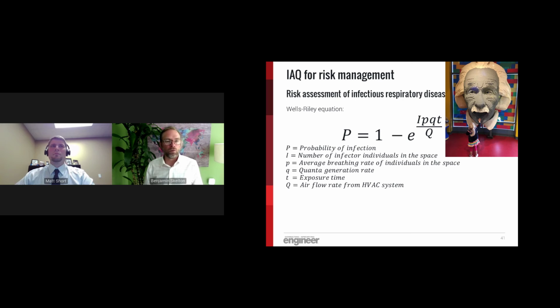So there is an equation called the Wells-Riley equation that was published years ago to help quantify the risk of infectious respiratory disease spread in buildings and spaces. This equation is very simple, very useful. And what it does is it helps you identify if you need to change something. If the ventilation effectiveness of your VAV system is not keeping the risk number acceptable, you may want to look at portable HEPA units and filtration in the localized space.